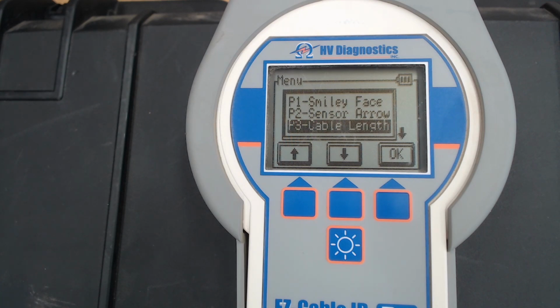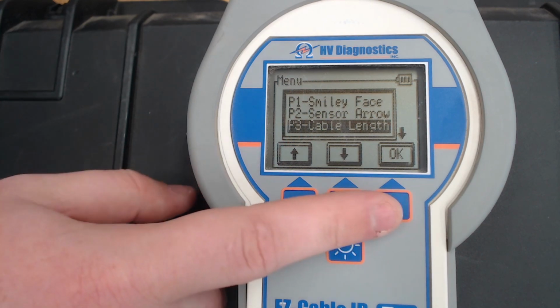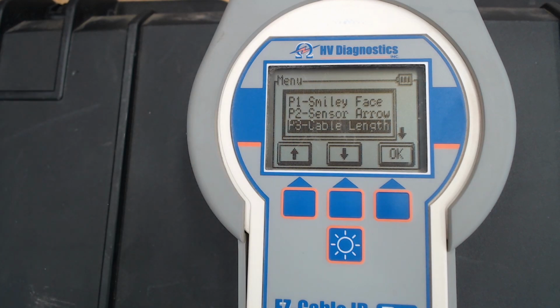I should have a negative signal on my return, but if my coil is faced the wrong way, it'll show me a positive signal. But I could still ID both signals with that bottom right button when I'm IDing. It'll show me positive L1, positive L2. And if I flip the coil the other way, I should get a negative L1 and a negative L2. So that's something to keep in mind with the transmitter, finding which way you have the coil placed, and that is the settings for the EZ ID.